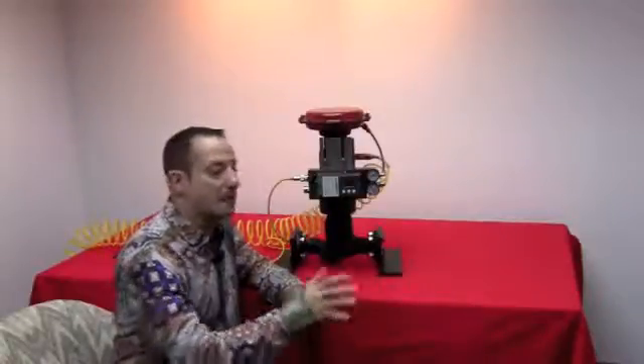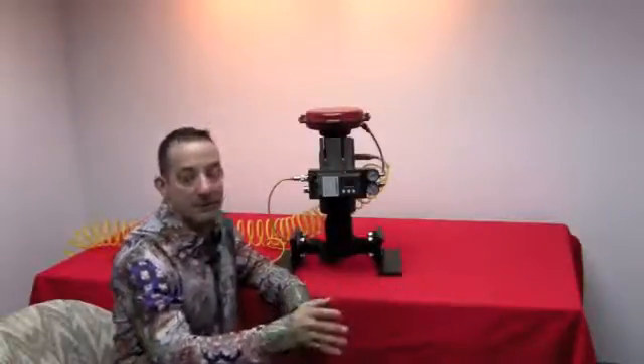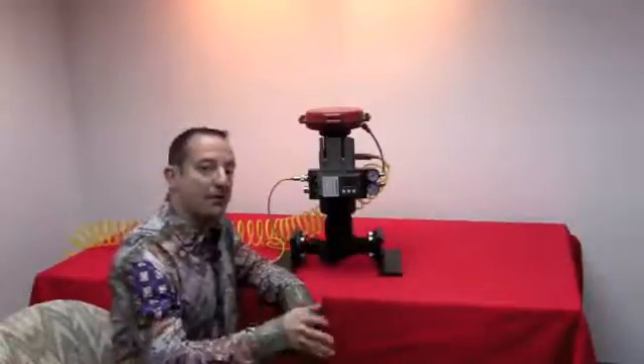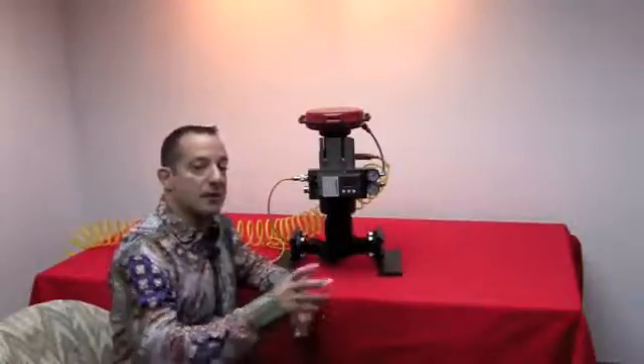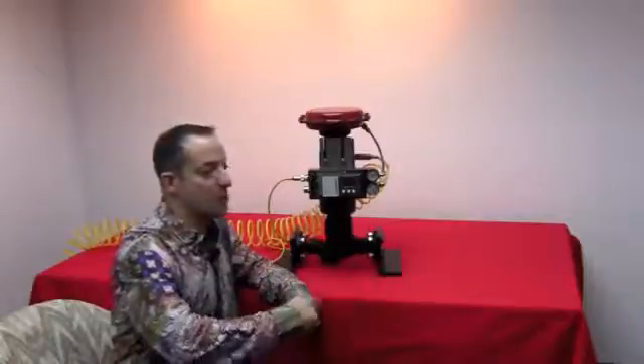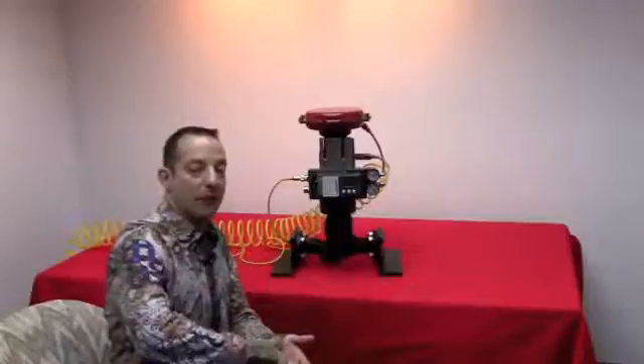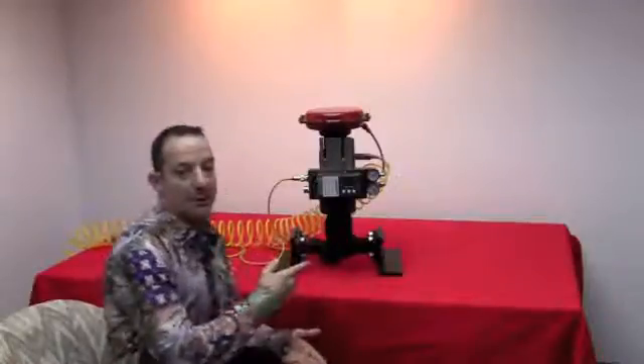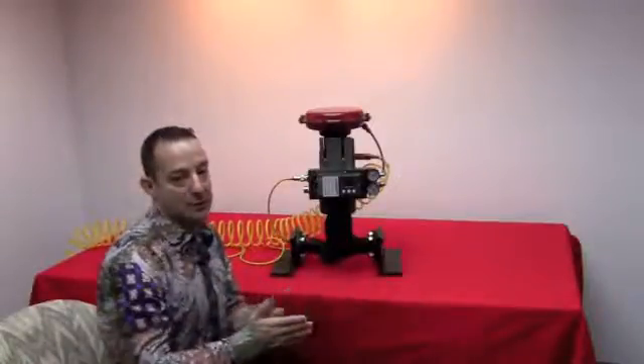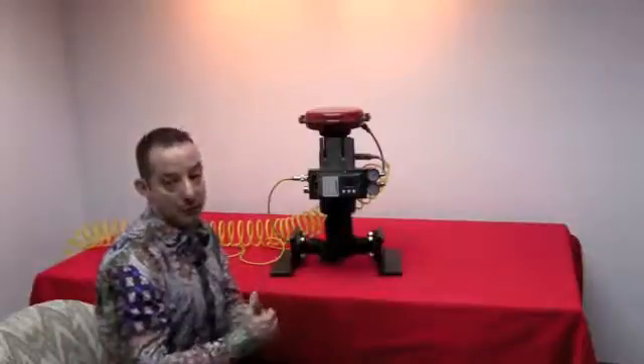It doesn't have to be exact. Somewhere between 48 and 52 is sufficient. But what this does is ensures that the stroke of the valve is centered in the 90 degree range of the potentiometer, so that you are able to control position over the full stroke of the valve.